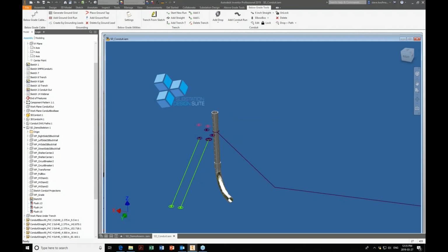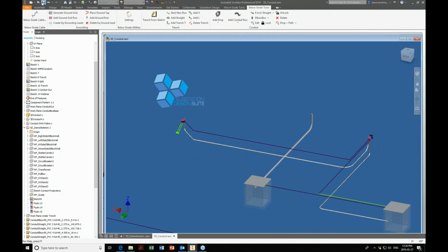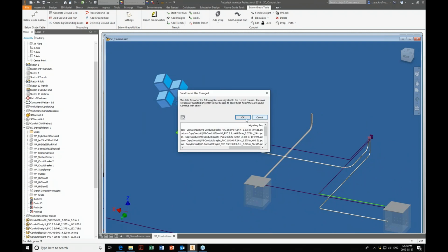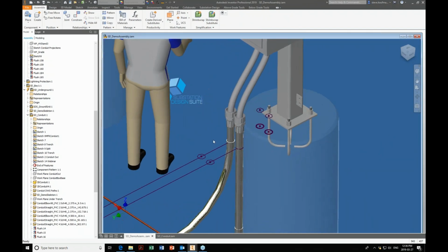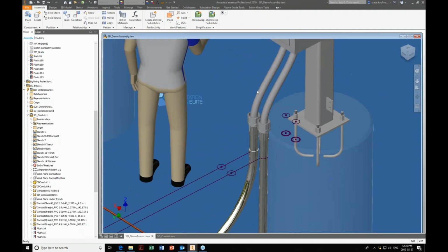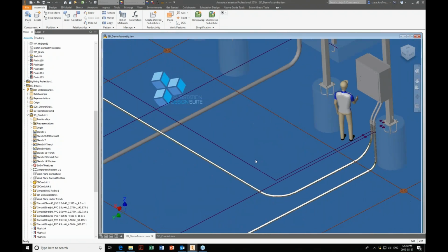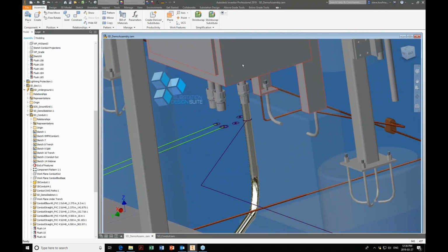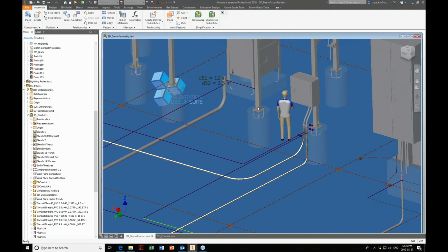So by leveraging the skeleton and coming in with these items, projecting where we want our conduit out from and where we want our conduit placed, we can be very accurate on how we come out of the ground here. So let's go back into this area. You can see how I'm right on the connections that are coming out of this box here, right? I've placed them exactly where I needed them to be. And we come down here, I have my drops in here. So we're able to do that exactly by leveraging the skeleton, and everything's going to be exact because everything's placed consistently.